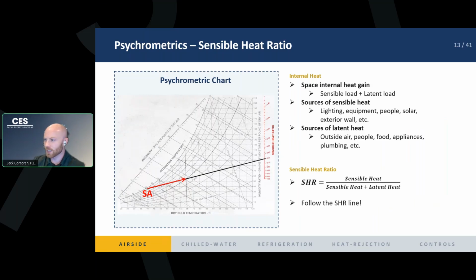Your sensible heat gain comes from your lighting, any piece of equipment, people give off sensible load, solar loads, exterior walls, etc. That's your temperature, not your moisture. And then your latent heat comes from your outside air, right? People give off latent loads, like sweating, or just people give off both sensible and latent loads. Cooked food gives off latent loads. Appliances like a coffee maker, and then plumbing, if you have like a pool or sinks with water and whatever, that adds latent loads into your space.